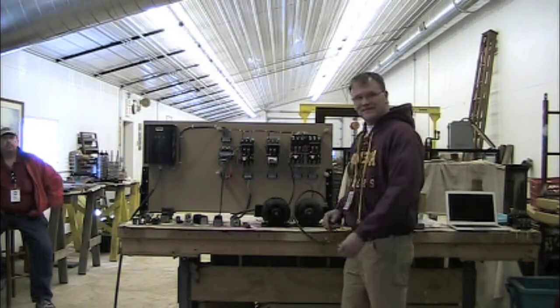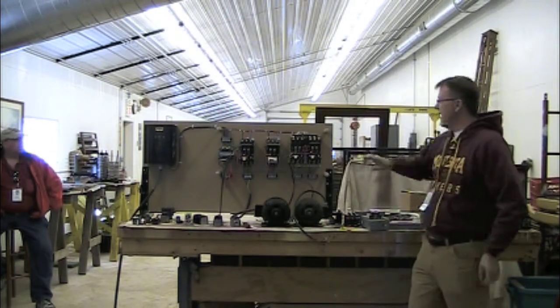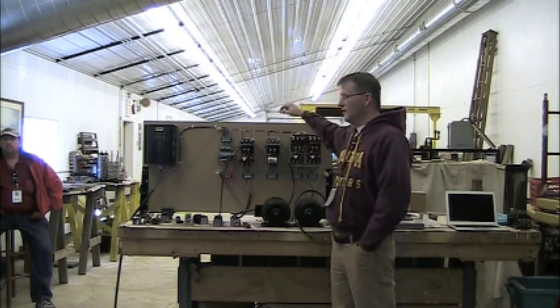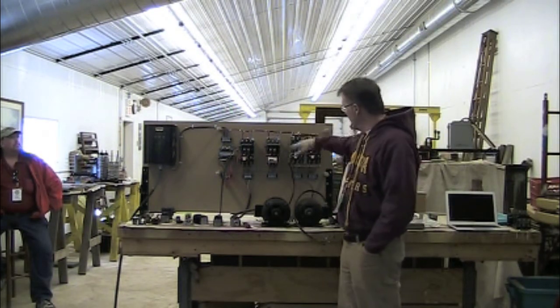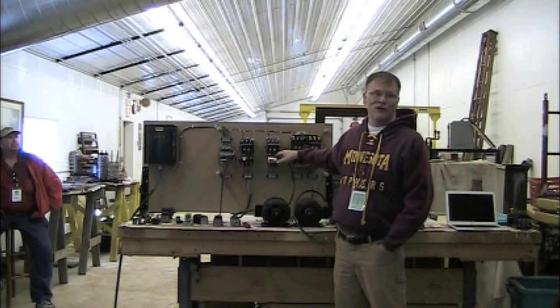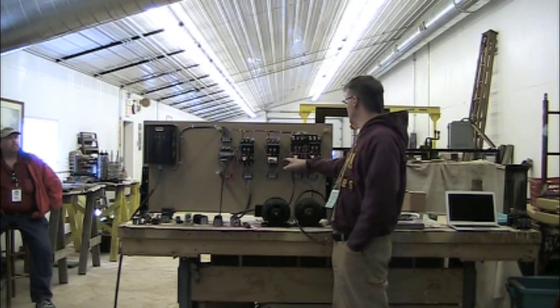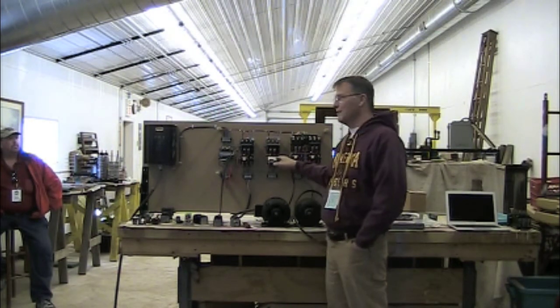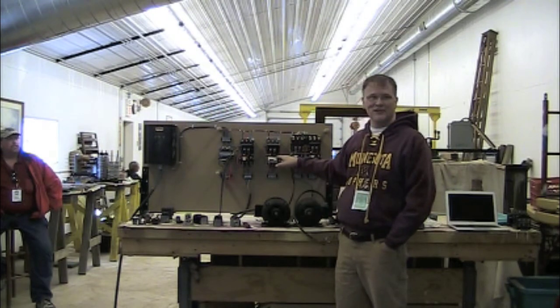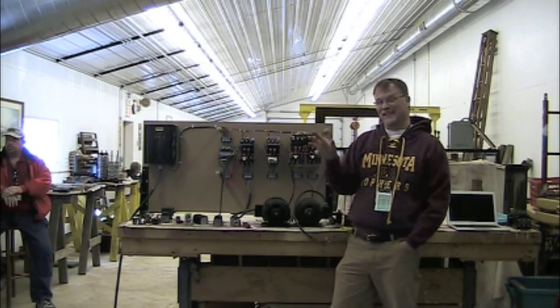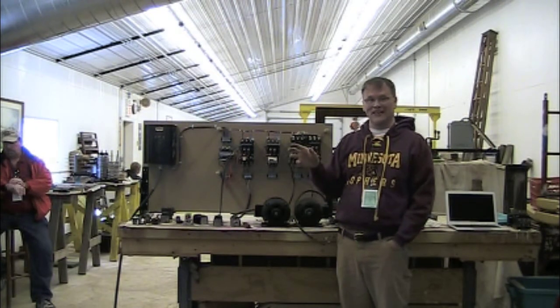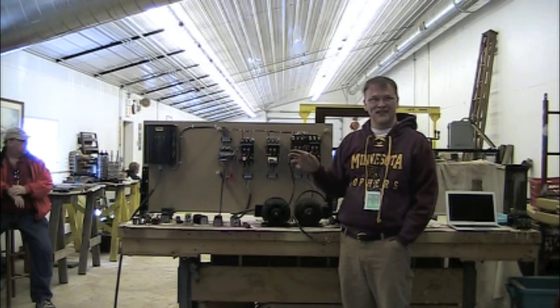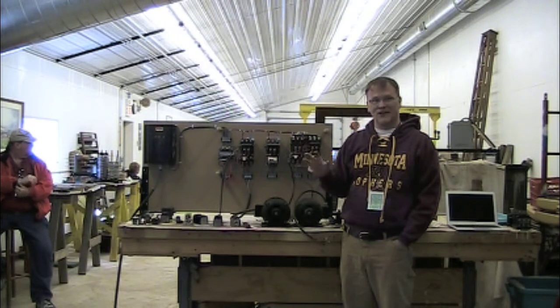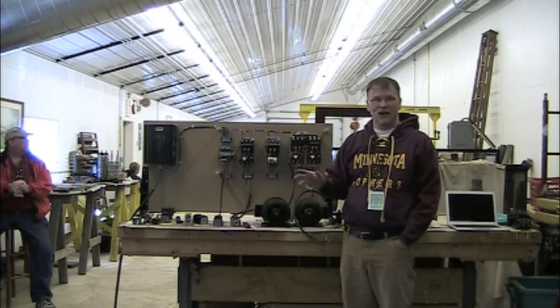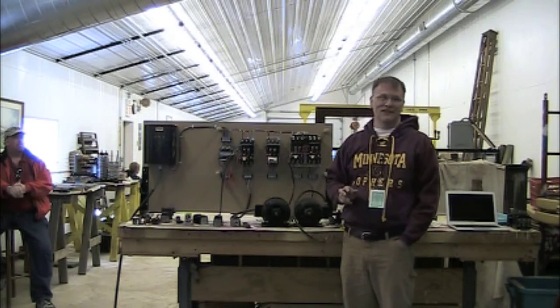So, the second one here is also a Bulletin 509, but it has a solid state overload block on it. It's a NEMA rated starter, but this is actually much more of an IEC type of device in here. Allen Bradley has really shifted now. They've got, I think, a 300 series or whatever. They have a kind of crossover lower price NEMA/IEC lineup now.